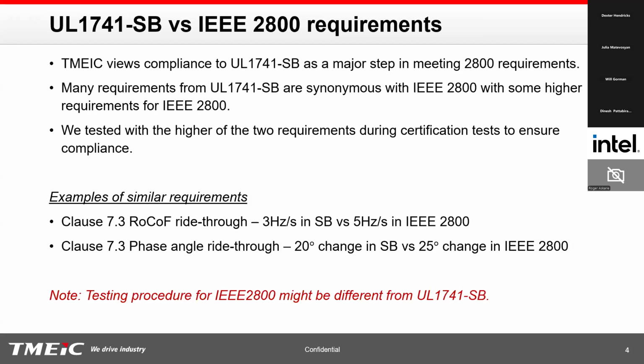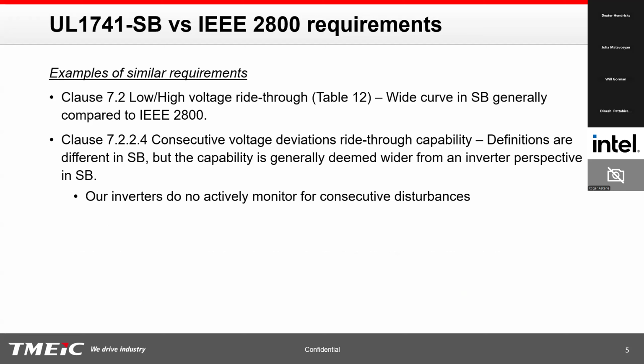One thing to note is that 2800 works at a plant level. It doesn't work at an inverter level. The 1741 certification is an inverter level certification. So we test these requirements at the inverter level, not necessarily at a plant level. And these are all tests performed in the lab under certain conditions. So the testing procedure for 2800 might be different from 1741 SB. That would depend on 2800.2. That would come in later.